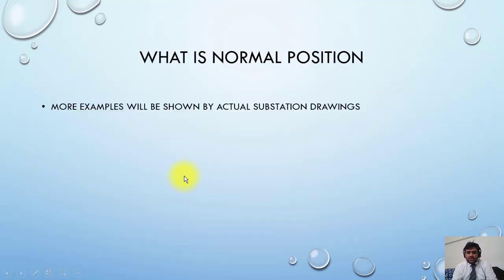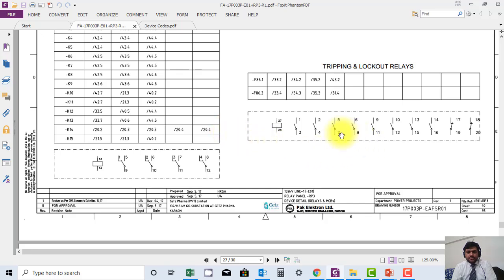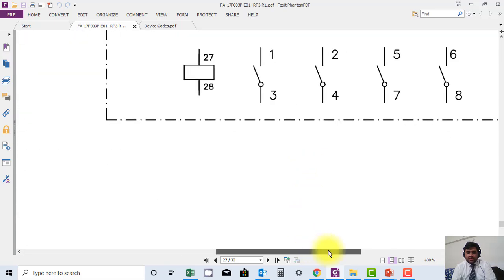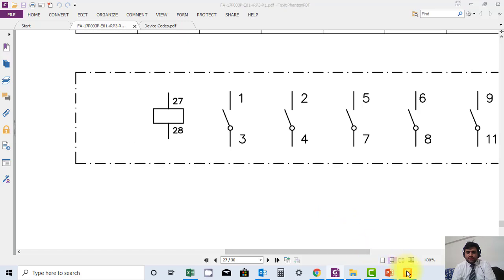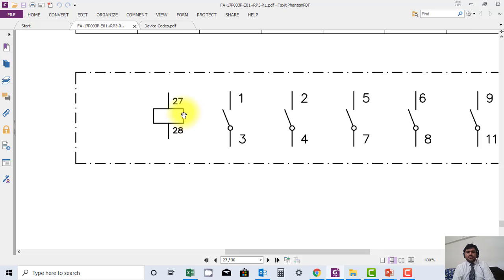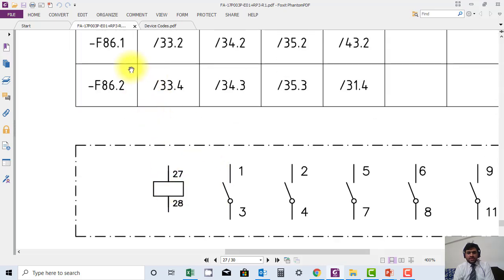Let us now go to the drawings and see these examples. Here you can see all the contacts are drawn open — this is drawn in de-energized position. Whatever position is shown here, for example this contactor — there are two contacts there.